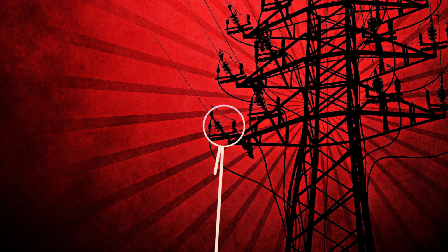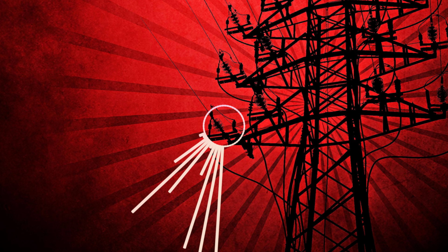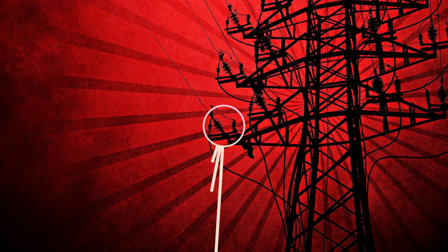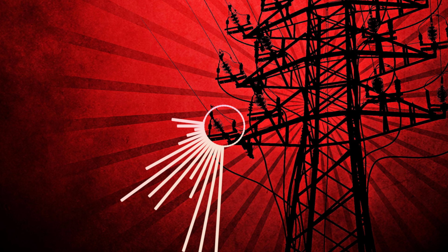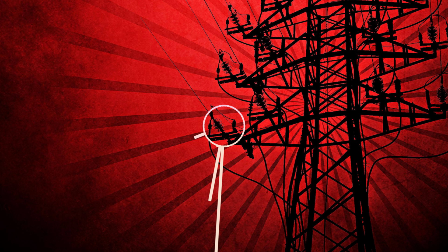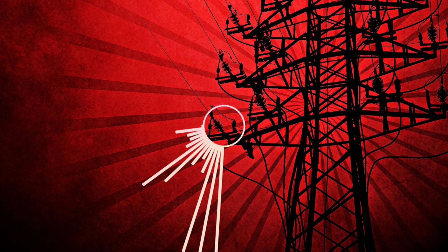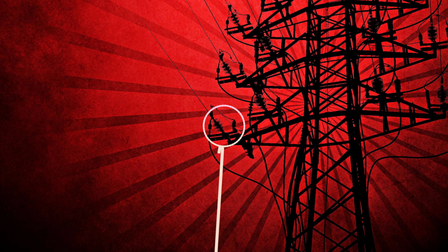For motors, which are often marked with letters like B, C, or D for design, wires rated 75 degrees Celsius or higher can be used, but the ampacity must not exceed the 75 degree rating.